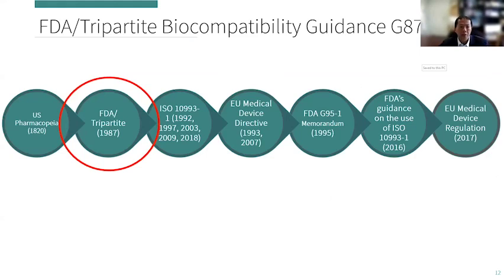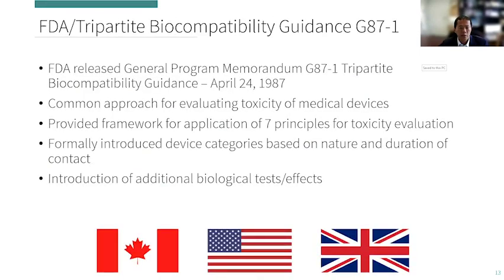Now switching gears from the USP to the FDA, in 1987 the first guidance document for biological safety assessment was published. This is essentially called the Tripartite Biocompatibility Guidance, or G87-1. This was a collaboration between Canada, the US, and the UK, where they wanted to develop a common approach for evaluating the toxicity of medical devices within those three jurisdictions.